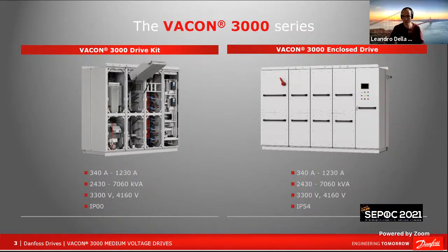Another thing that is offered is the front end of the drive. We offer the traditional diode front end, which means we have an uncontrolled rectifier on the input section, and of course a filter to mitigate harmonics. But we also offer the active front end rectifier, meaning it's basically a three-phase inverter that's mirroring the output of the drive. So it's really producing very low harmonics, and it's helping the grid to some extent.